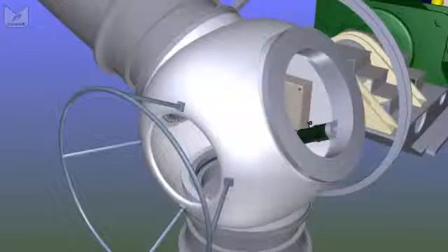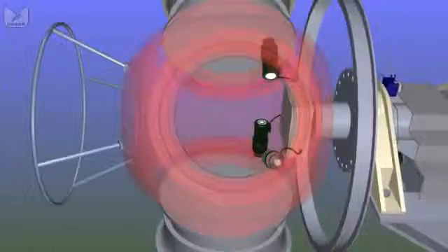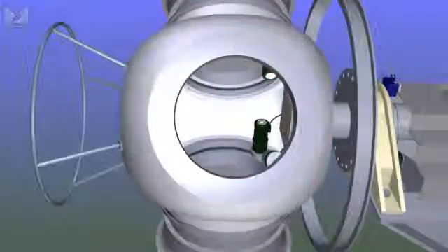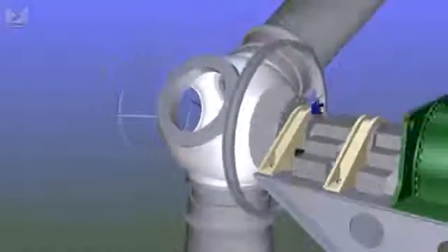of the hub, and inside the hub we'll find the control electronics, the pumps, the motors and the batteries to control the pitch of each blade, rotating it on its own bearing to set the optimum angle for the wind. If we turn the blades through 90 degrees so they're edge on to the wind, there's no net turning force. It's a process called feathering, and the turbine will stop.